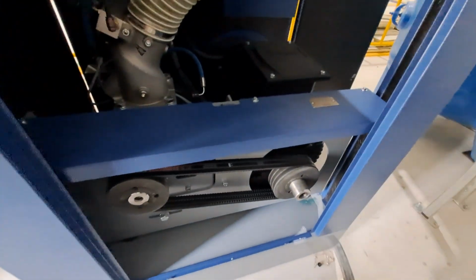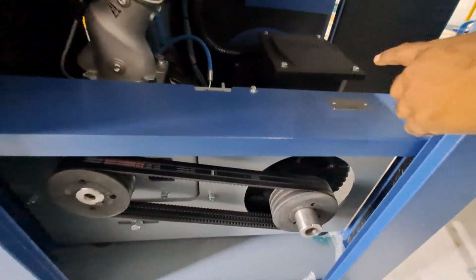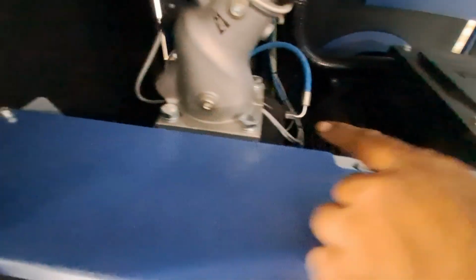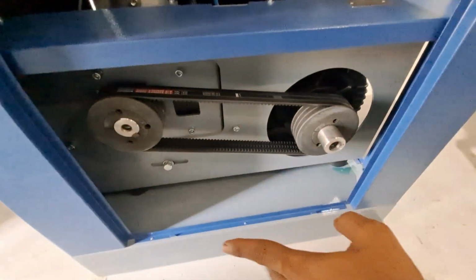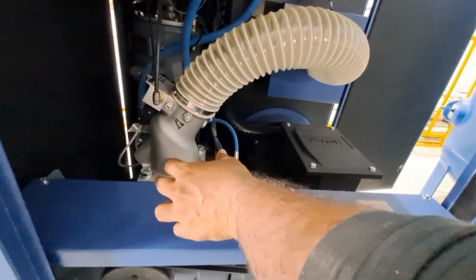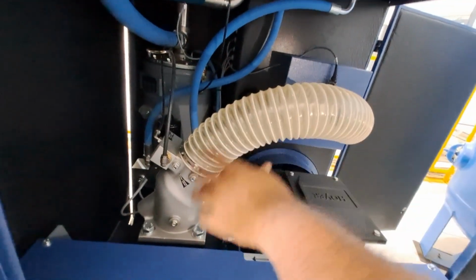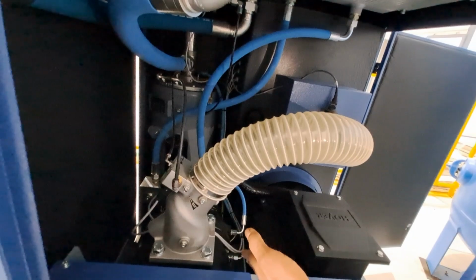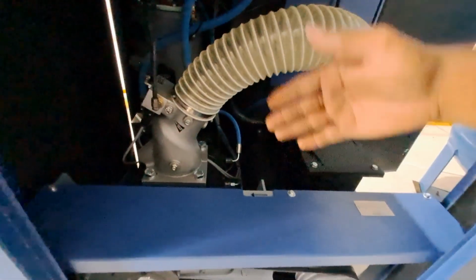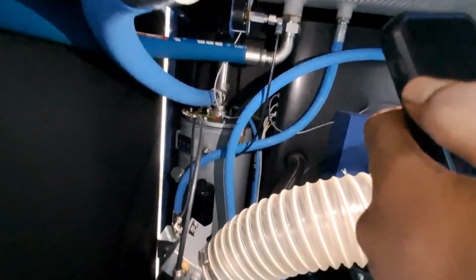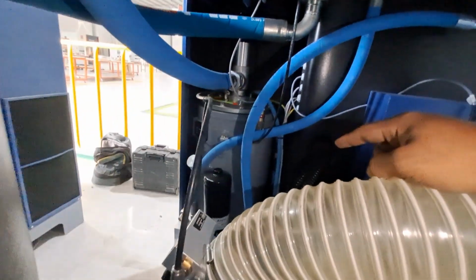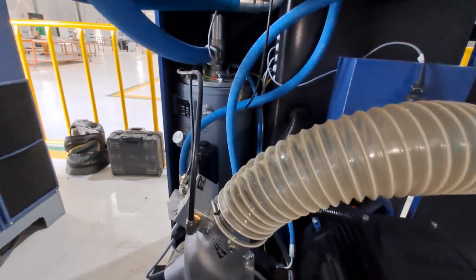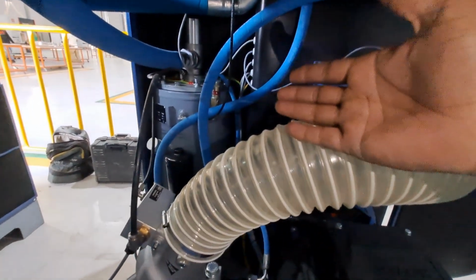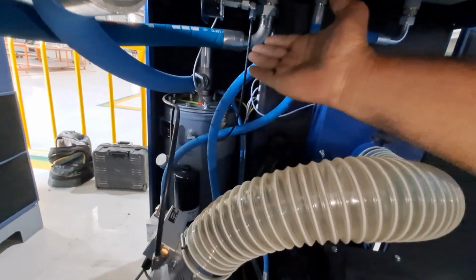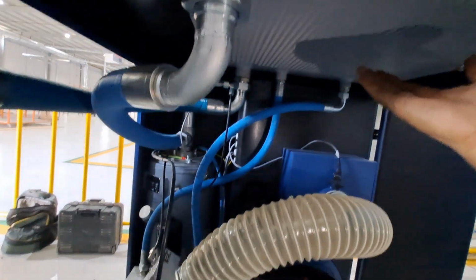This is driven by belt. This is the main motor and this is the air end. These both are driven by belt. This one is the intake valve. From here air will be sucked inside and will be compressed here. From the air end it will go to the tank, the oil separator tank. In the separator tank there will be separation of air and oil, and after separation, the air will go to the cooler, the heat exchanger.